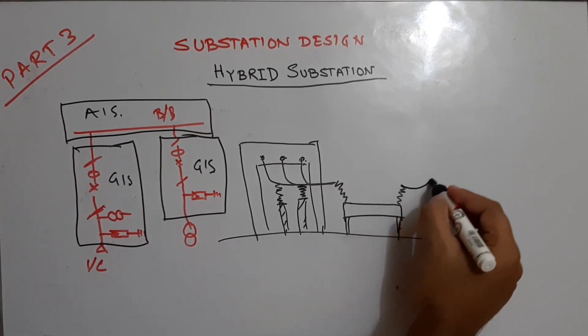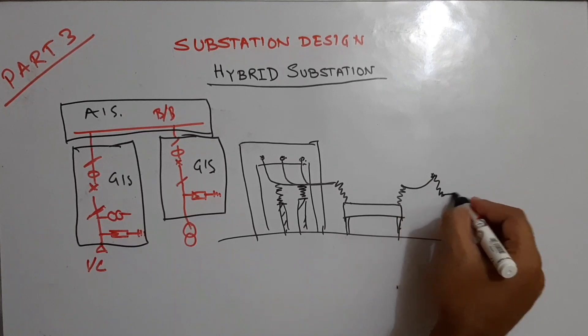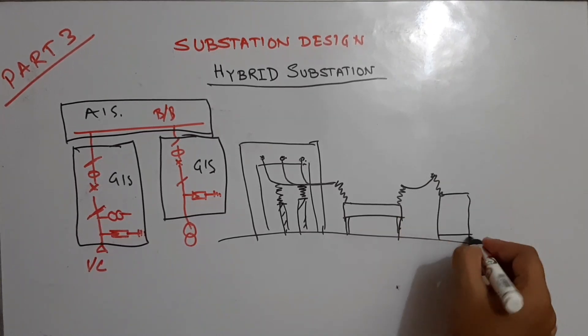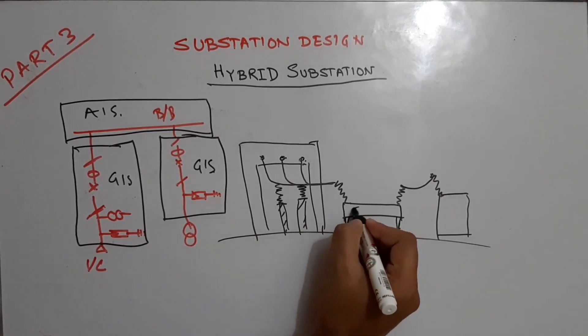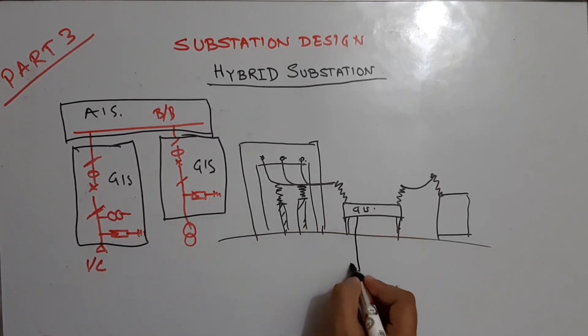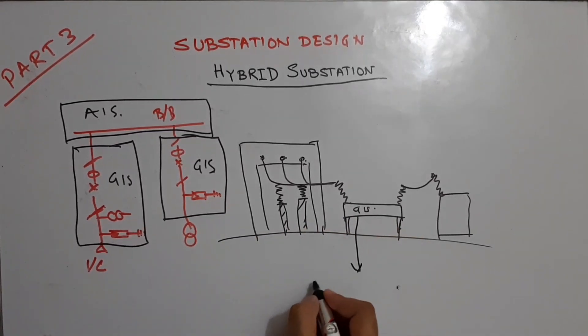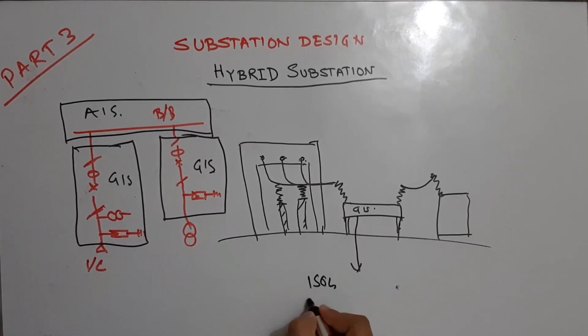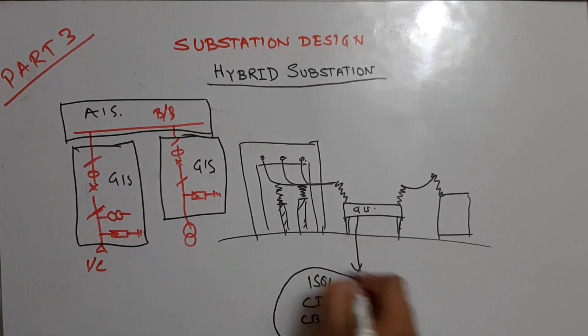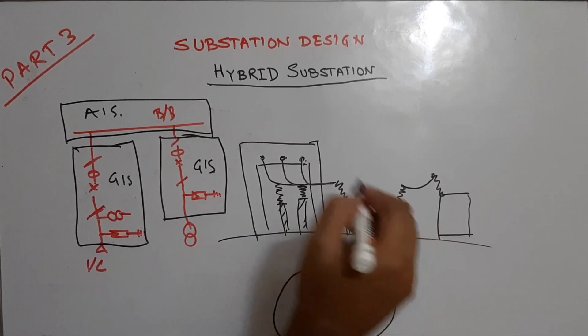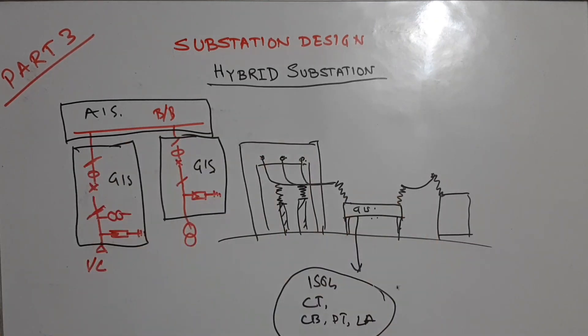From the GIS structure the transformer feeder connects to the transformer. Inside the GIS assembly we have the isolator, CT, circuit breaker, PT, and lightning arrester — all enclosed within the gas insulated switchgear. This is what forms the hybrid substation.